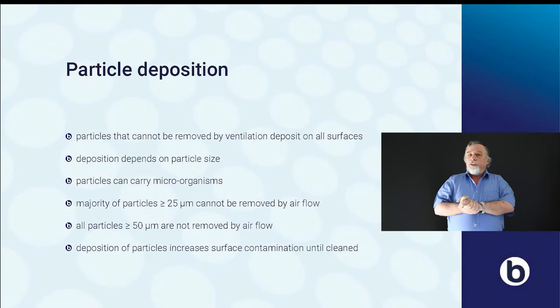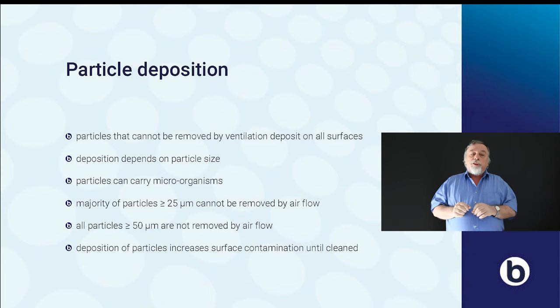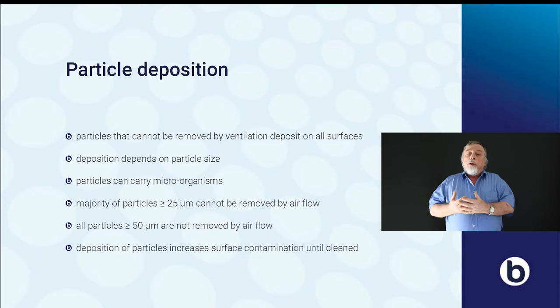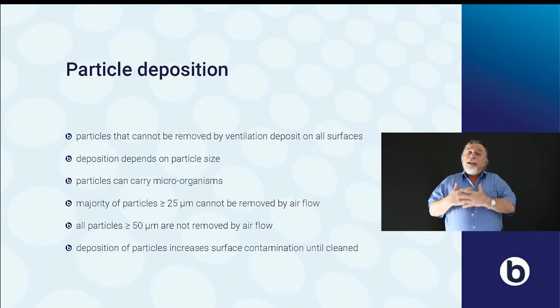Particle deposition: particles that cannot be removed by ventilation deposit on all surfaces. The deposition depends on the particle size. Particles can also carry microorganisms. The majority of particles larger than 25 micrometers cannot be removed by air flow, and all particles larger than 50 micrometers will not be removed by air flow and will deposit on all surfaces.